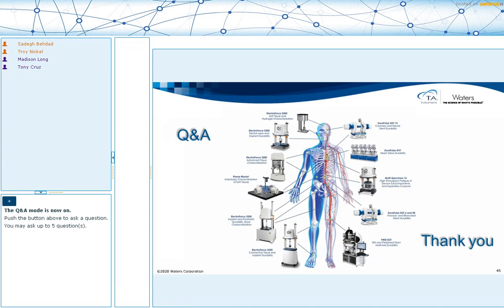So the questions here are, let me take one here that says, can I change the loading level after my test started, or do I need to stop and restart it? Yes, you can change the load level as your experiment is going on, because we know that when you want to create the S-N curves, it's important to maintain the stress level for the whole duration. As you're exposing this material to stress, you start to generate micro cracks or small failure points inside it before it eventually breaks. So you see a decrease in the stiffness with time.